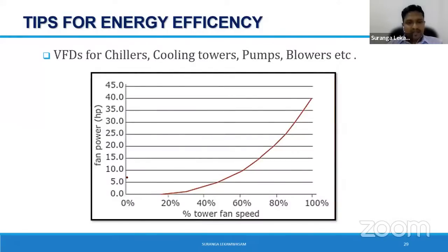Then the use of VFDs. You know the beauty of VFDs when you use them with motors: if you reduce the speed by 20%, it reduces the power consumption by 50%. Because this is a square law rule, an exponential variation. If you unload your VFD chiller, or your cooling tower fan, or your AHU blower or pump by 20%, you get a saving of 50%. That is a huge saving. Therefore, wherever you can apply, you must think of having these VFD drives.